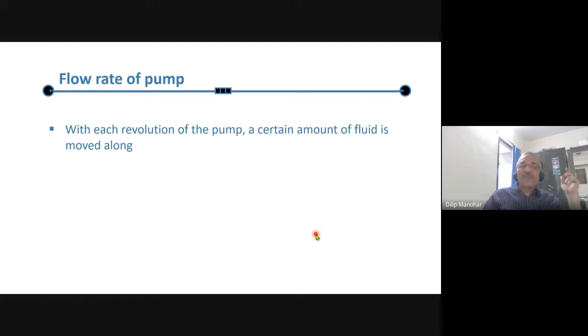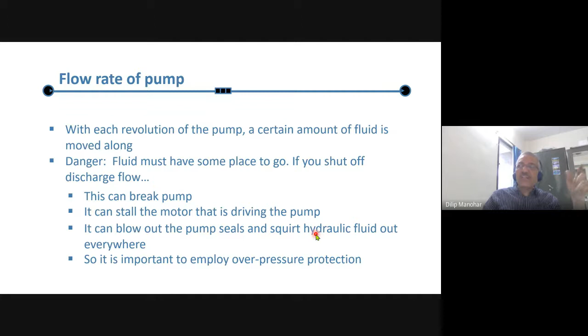Then what will happen? The prime mover will move the pump, but there is no escape on the discharge side, so it will break the pump. So there is a danger in the positive displacement pump, and you should have all safety mechanisms installed. It can stall the motor, break the pump, or blow the seals, and fluid will be discharged everywhere. So you need some mechanism to protect against overpressure. That means you require an overpressure protection device in a pump. Normally, most pumps have a built-in safety device, but in hydraulics, we use an external safety device.